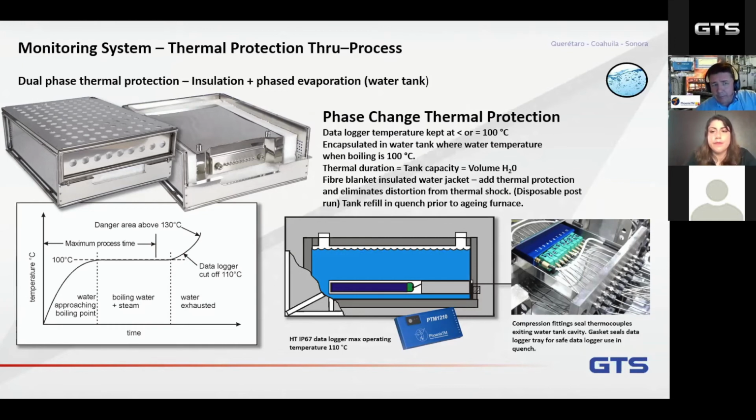At the top here, you've got the barrier, but there's a cutout diagram here or a photograph showing you the inner core. This is the water tank. And around that water tank, there's a structural encasement. And there is also an insulation blanket, which slows down the absorption of heat by that water tank. Now, interestingly, because the logger is in the center of the tank, it's in a tray which is completely sealed. So any moisture or any water in the quench tank when it's submersed can't get to the data logger and cause any damage. All right.